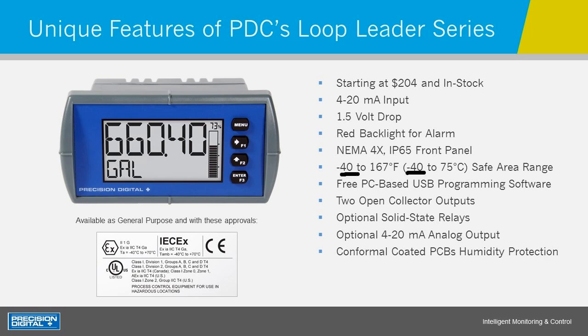Again, -40 is something to keep in mind whenever you're talking about 2-wire devices in a cold weather environment. Our LCDs go down to minus 40. Why do ours go down to minus 40 and no one else's does? Well, because we work harder at it. We work with an LCD manufacturer that makes us custom displays, and we've been doing this for years. So we make sure our displays work down that low. The programming software for this is free, and you can download it at our website, predig.com.